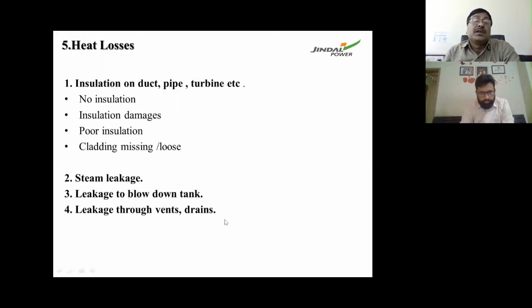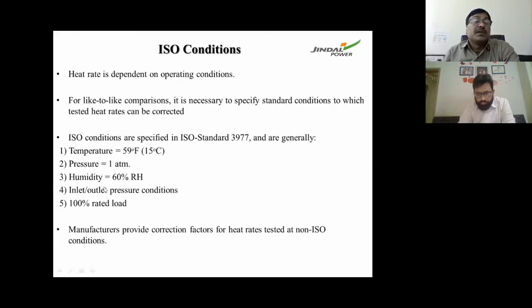Generally, heat rate is monitored and tested, and efficiency tests are conducted. There should be some standard during the efficiency test, because each time the ambient conditions may not be the same. So we have to apply various correction factors, and the result should be compared as per the standards. Normally, in ISO standard 3977, temperature should be 15 degrees, pressure 1 atm, humidity 60%.